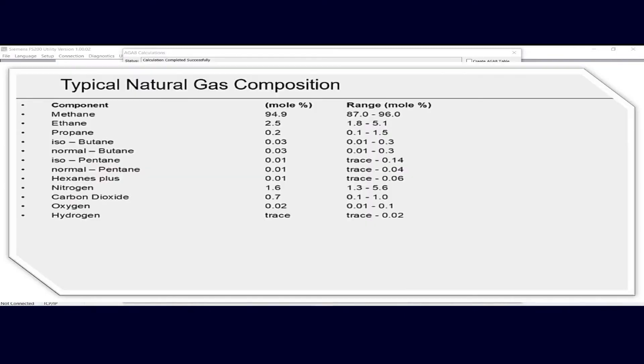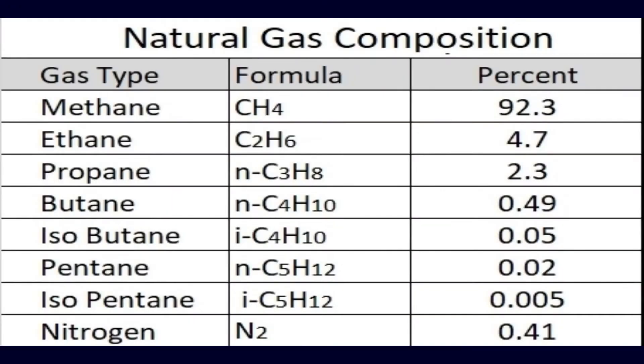Next, we'll look into actually creating an AGA-8 table that you can upload to your FS-230 flow meter. The FS-230 flow meter comes equipped with a built-in AGA-8 table that it references while measuring. If your natural gas has a composition different from typical natural gas, or in the case of a fixed gas composition, you want to perform standard volume flow measurement locally at the flow meter without the need for a flow computer.